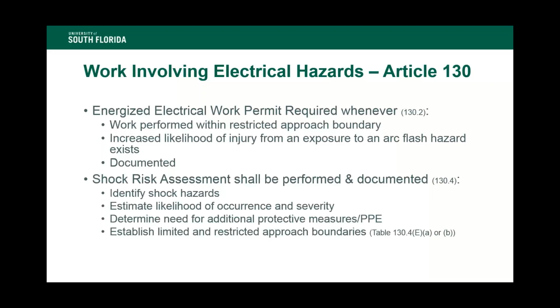So under Article 130, and this is in Chapter 1 of 70E, it states that if we're going to be working on live equipment, we have to have an energized electrical work permit. And that's basically required whenever work is being performed within the restricted approach boundary, or there is an increased likelihood of injury from an exposure to an arc flash hazard. And this electrical work permit has to be documented. It has to be an on-paper instrument.